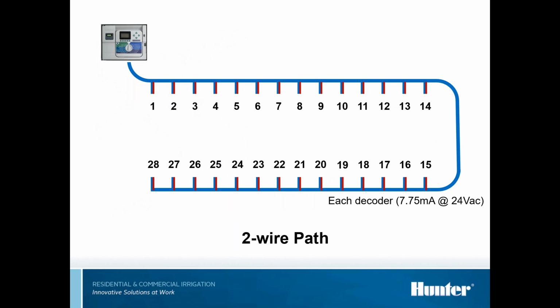Here's a typical 2-wire path leaving the controller, and you can see each decoder, if that 24 volt is hooked onto it, is going to be about this one right here, about 7.75 milliamps per decoder. When you hook the 24 volt power supply, if you look at it, you have about 28 decoders, and 28 times 7.75 is about 217. Remember, it's disconnected from the controller. Halfway, using the halfway method, it's about 105.